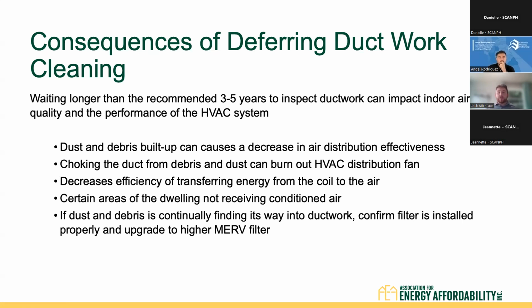Like I mentioned, certain areas of the dwelling not receiving conditioned air, and then if dust and debris is continually finding its way into ductwork, confirm the filter is installed properly and upgrade to a higher MERV filter. If you're just in a place that has a lot of dust, a lot of contaminants, or if you're in a unit with pets, you should consider upgrading the filter to a higher MERV filter, so a higher filtration rate. Next slide, please.